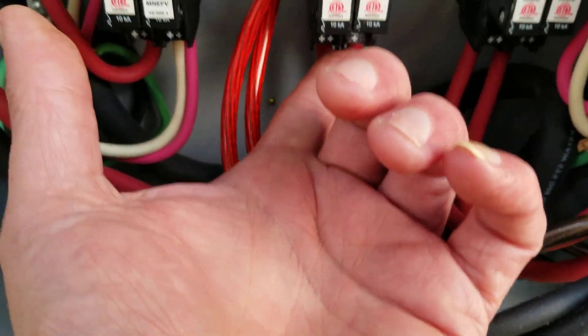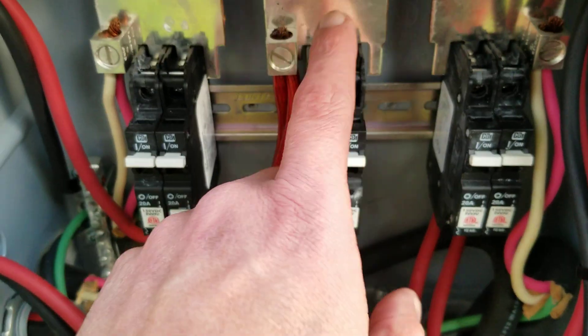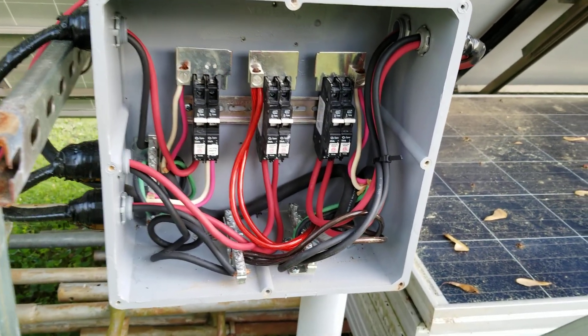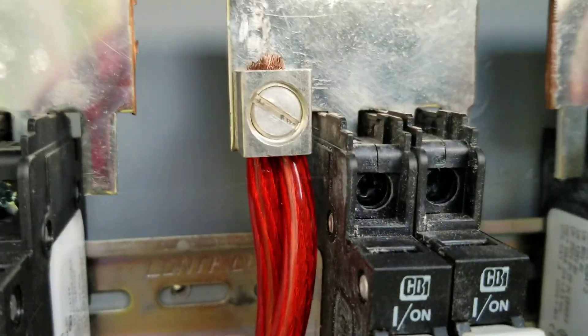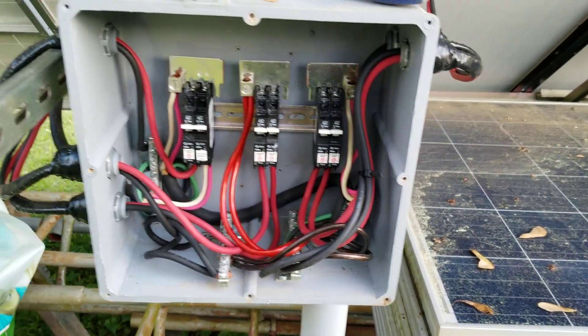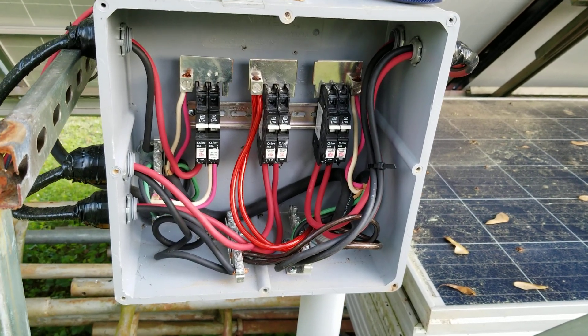Always remember: your positive input ends will always come in at the bottom, and your output will be at the top. That's something they don't always tell you about these DC MidNite Solar breaker switches — there is a positive and a negative. Look right there on the very bottom: plus for positive, that's your input side. The top side will always be your output side on those DC breakers, every single time.